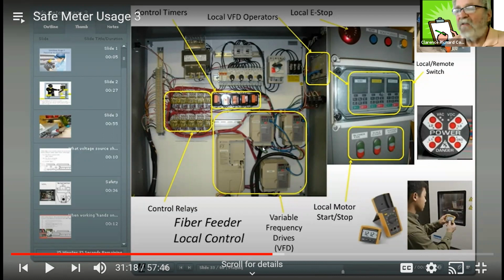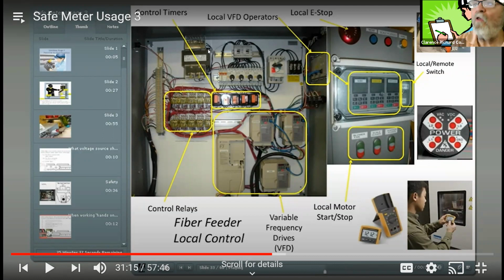A lot of times, if there's some 480 volts in there and some open terminals, I'm always leaning back so I'm not going to fall in, and no one's going to come by and bump me, or a door slam closed because of the wind. If I were to do this one all over again, all the 110 would have been in one box, and all the 480 volts would have been in another box. So if I want to do some work on the control part of it, these would have been separate.